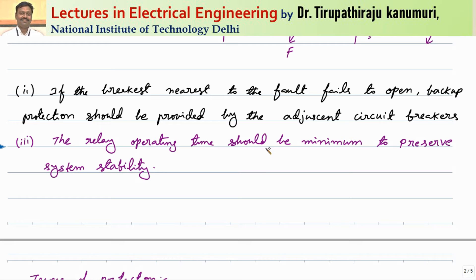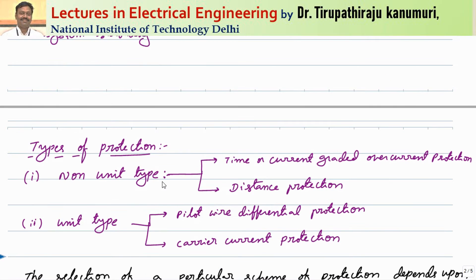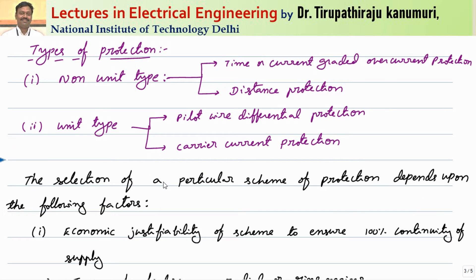The relay operating time should be minimum so that system stability is not affected. The different types of protection can be broadly categorized into two types: non-unit type and unit type. Unit type means one particular part of your transmission line or a particular zone is protected. Unit types include pilot wire differential protection — we have seen differential protection in module number 3.